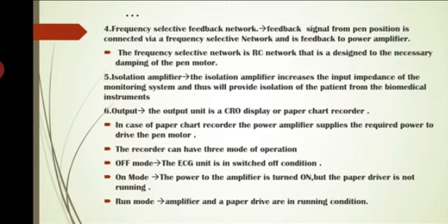In the paper chart recorder, to record the ECG signals, they are using wax coated paper and a heat sensitive pen. So whenever the heat sensitive tip moves on the wax coated paper, we get the recording of the ECG signals.